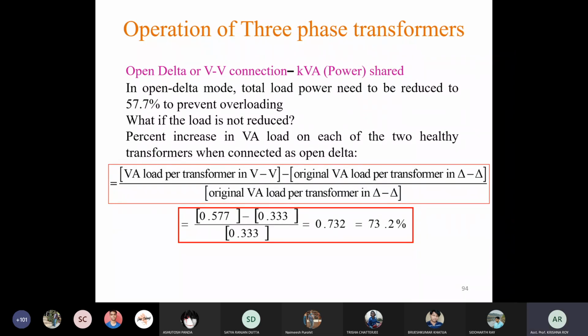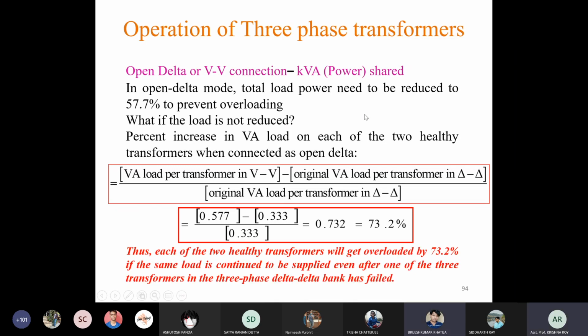So that is a huge amount of overloading, and the transformer will get damaged. Therefore, the same conclusion: each of the two healthy transformers will get overloaded by 73.2% if the same load is continued. As per our example, if we still continue to supply 60 kVA, each transformer will get overloaded by 73.2%. And what will be the effect? Both transformers will get damaged.